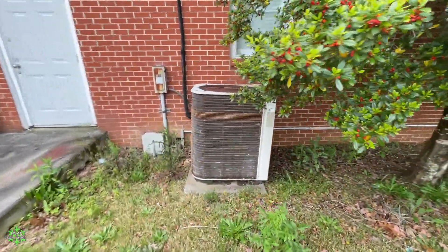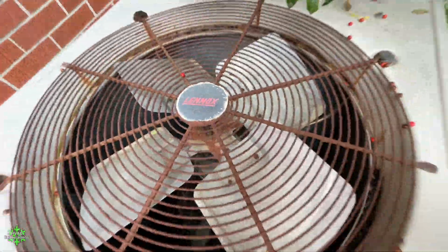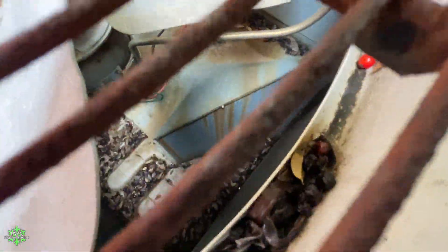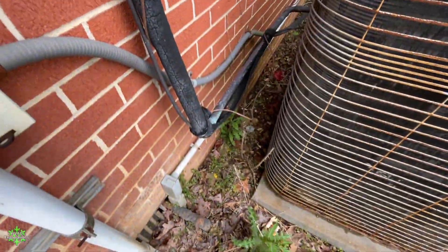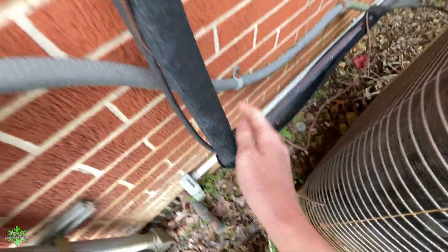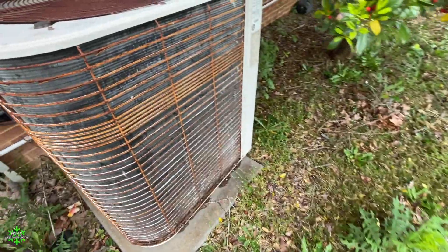We are turning a corner at a church and we're gonna see what kind of units we've got. We have a Lennox unit here — this is an elite. It's got a compressor guard. I think all these older Lennox units have a logo on this model. It's a 510 from 1998. There's the disconnect. This is definitely bigger than a 5-ton — look at how big that suction line is, and the line's kind of moving freely.